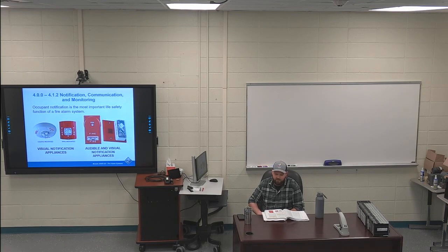412, audible notification devices. So this is your sirens and your horns and stuff like that. Top right of page 29, where you see NFPA 72 through the end of the paragraph is highlighted. NFPA 72 specifies that the standard signal, known as the temporal 3, is required by most fire alarm systems. You need to know what the temporal 3 means, including household systems. This signal has 3 half-second tones, a pause, and then it repeats the pattern until the alarm is manually reset.